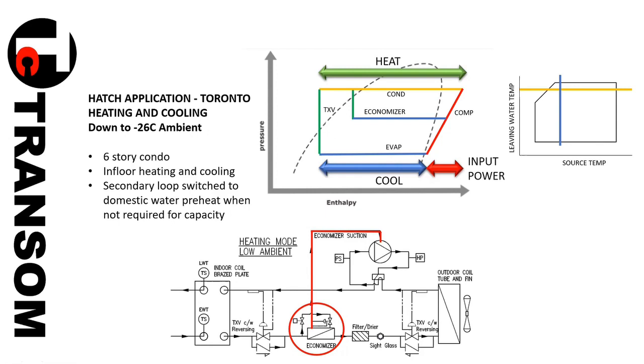Now, with that, you end up with basically vaporized gas, and the compressors they use with it have a vapor port, I call it. So they have the regular suction port, which takes in the suction gas and starts compressing, and then the vapor port opens up, and that's where we squeeze in the vapor gas, and then it compresses it some more, and it goes out through the discharge. So it's two different ways of doing the same thing, but the net effect is the same.